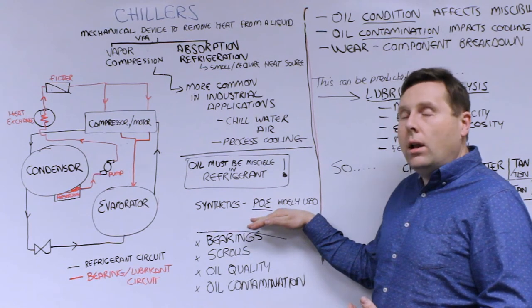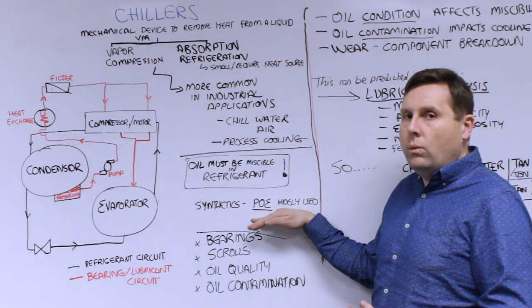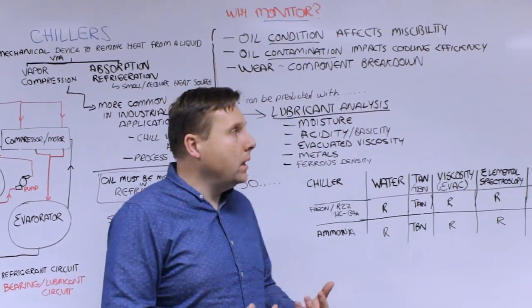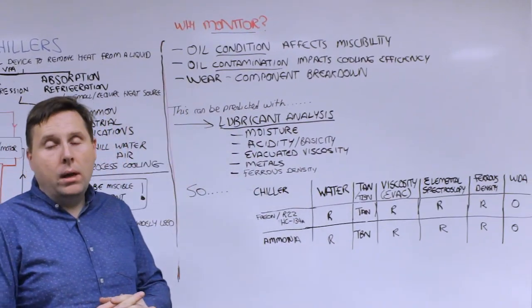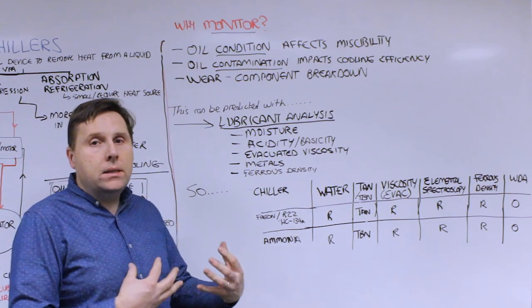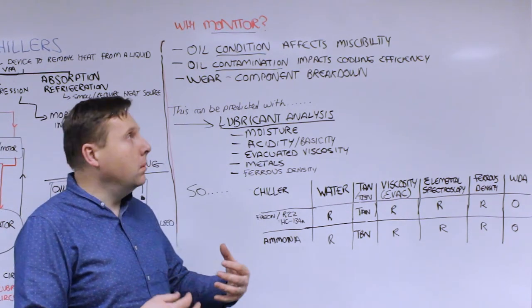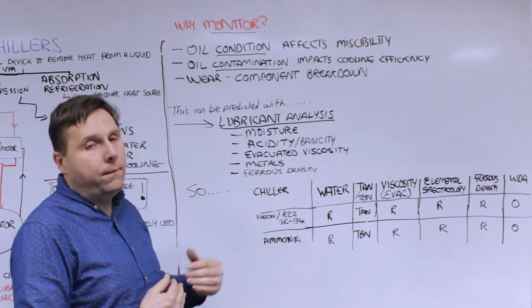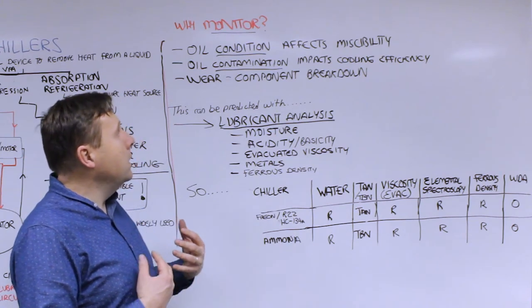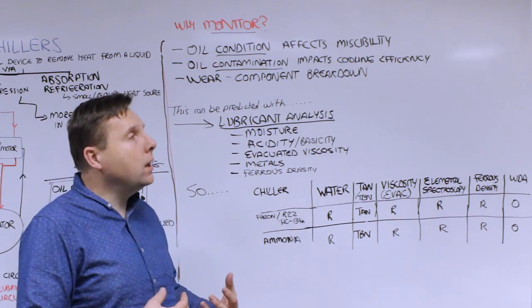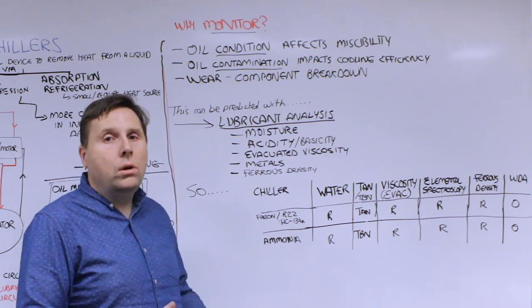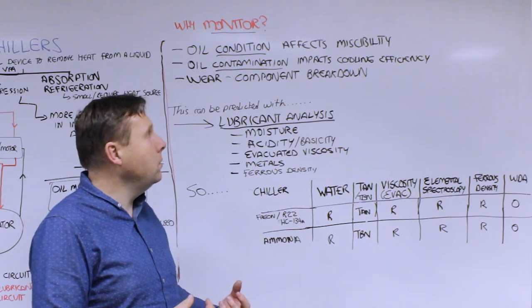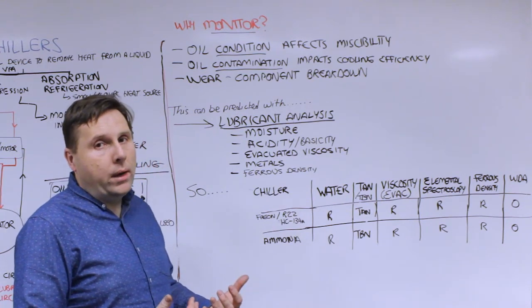Why are we monitoring this? We want to look at the oil condition because since the refrigerant and oil have to be miscible, the condition and type of oil affects that miscibility. In addition, any contamination such as moisture getting into the system affects the cooling efficiency and the ability of the chiller to perform its primary function.